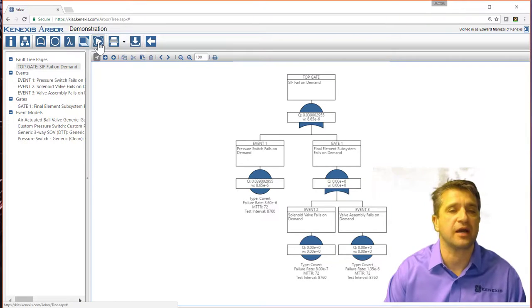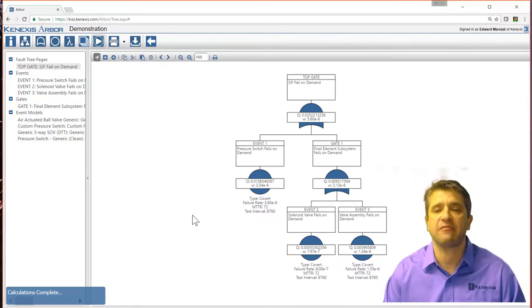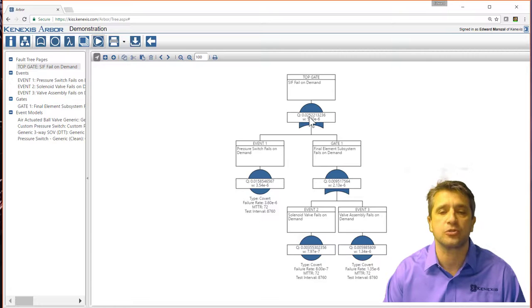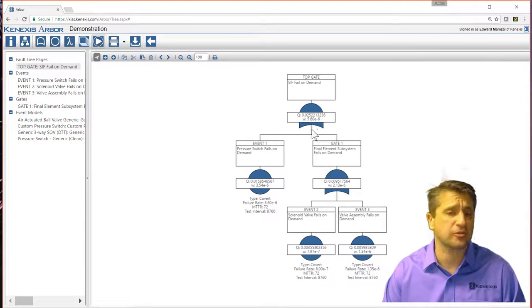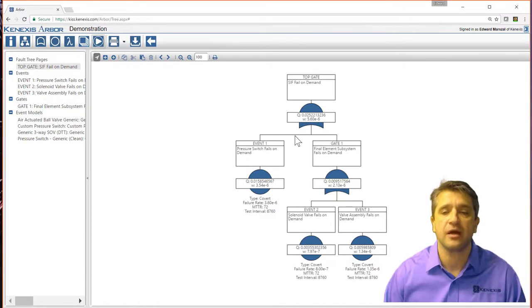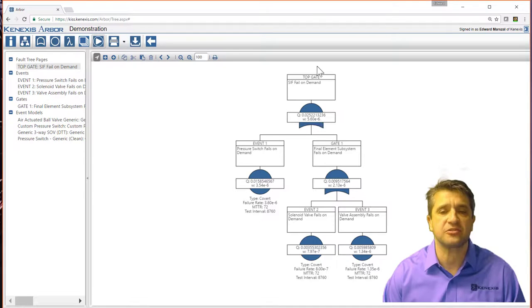If I want to run calculations, I go again to the run calculations button on the action ribbon. And everything is calculated out. So my probability of failure on demand for this system is 0.02. And it also calculates frequencies. This would be the dangerous failure frequency. So we're calculating all those items throughout the fault tree.